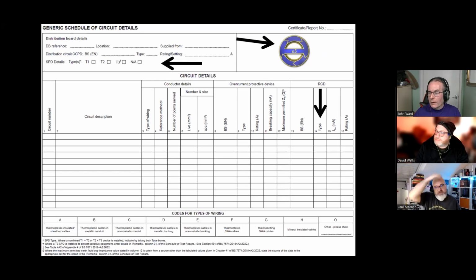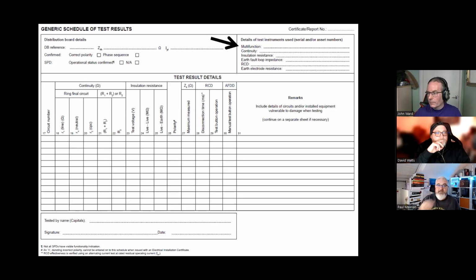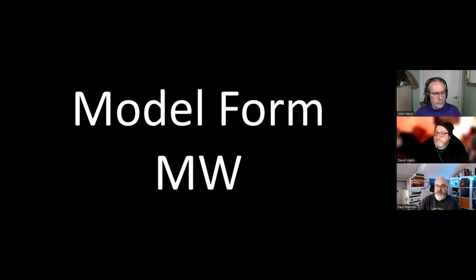One of the good things is that they've listened: the old, really compact form has now been split into two. So, generic schedule of circuit details. They've got an inclusion for SPD type. They've got a place for your company logo. And they've also got on the RCD column an ability for you to put what type of RCD. So that's just the circuit descriptor and the circuit information and protective devices. There's then obviously a schedule of test results, where, as John said earlier on, they've just looked at what other people are doing and spread it out. And there's now at the top, they acknowledge multifunction testers, because that's what a lot of people use now. And that's pretty much it from an electrical installation certificate and schedule.